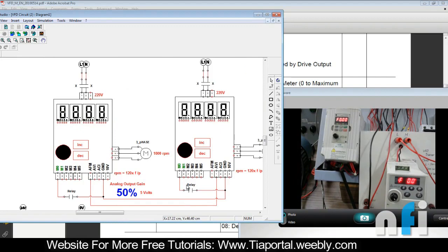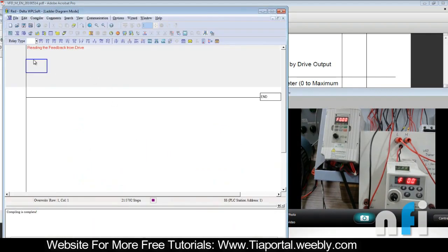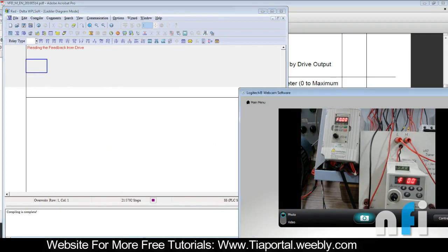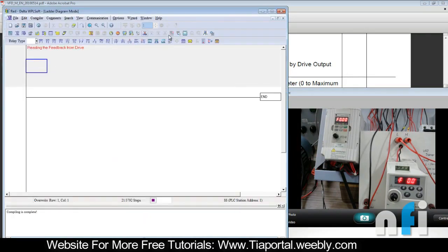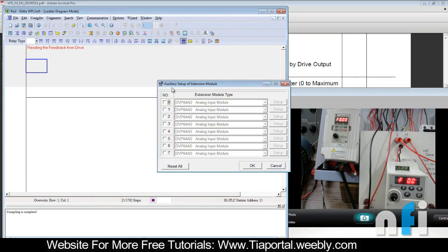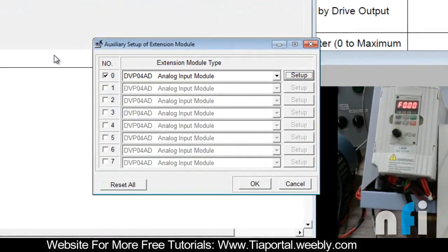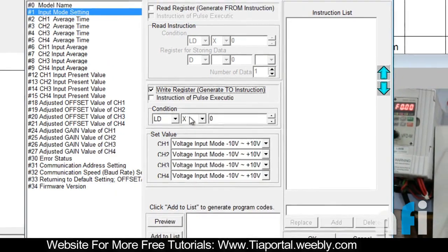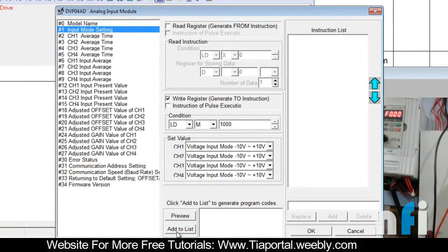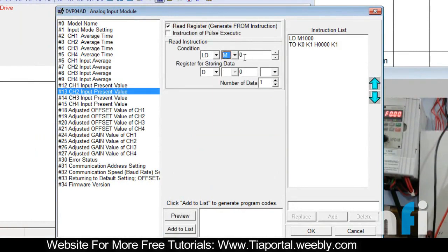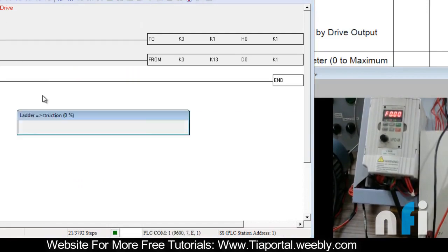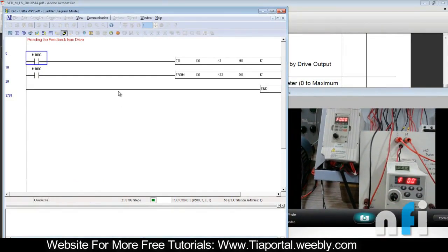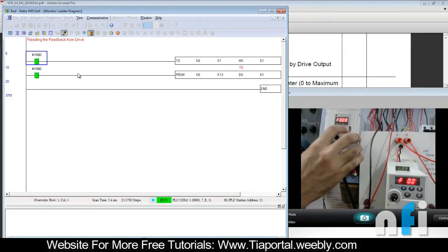If you want to read this feedback, I can quickly show you. This AFM wire is also going to channel 2 of my analog input module. Let me set up the analog input module: voltage mode, channel 2 present value, since it is connected to channel 2. Going online now — when I run the drive you can see the feedback: at 3 Hz it's showing around 900 something pulses.